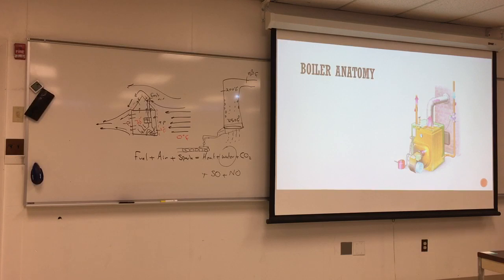Again, we talked about efficiency before, right? Yeah, there's combustion efficiency, and there is thermal efficiency. This 95 is thermal efficiency. How much heat are we getting out of the combustion we made? For combustion efficiency, it's very difficult to go above 90.